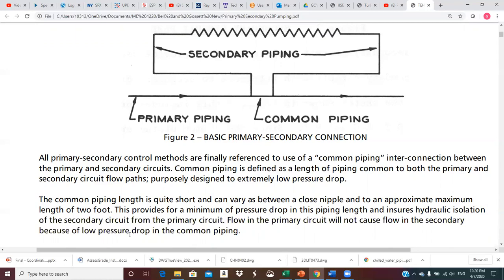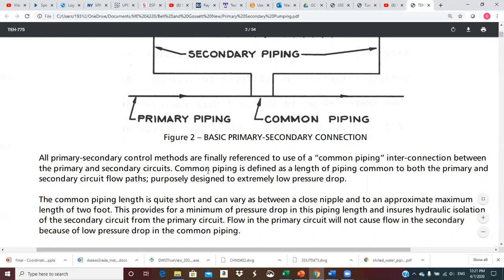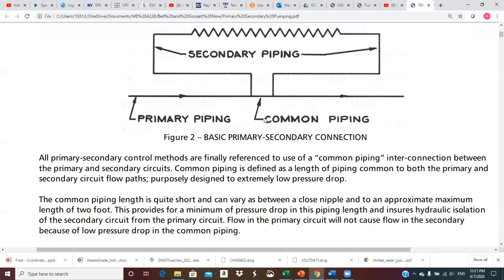The common piping length is quite short and can vary between a close nipple to an approximate maximum length of two feet. This provides a minimum pressure drop in this piping length and ensures hydraulic isolation of the secondary circuit from the primary circuit. Flow in the primary circuit will not cause flow in the secondary circuit because of low pressure drop in the common pipe — no delta P across it. Important fundamental concept.